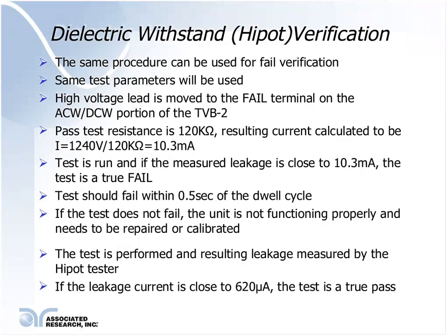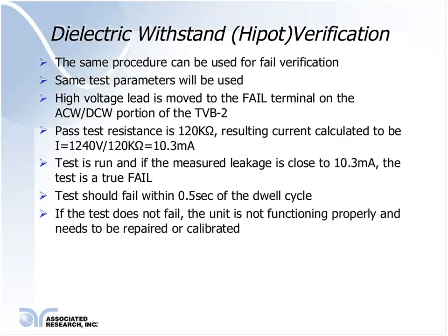The only difference here would be that on the fail side, the TVB2 box is utilizing a different resistor, which is the 120k ohm resistor.